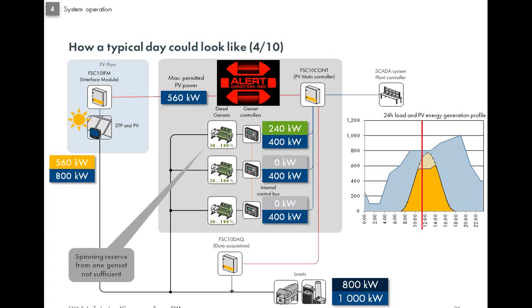Now let's assume that one generator tries to shut down because it thinks that it will take care of the load entirely by itself. If that starts to happen, our system will give an alarm and it will make sure that there is sufficient spinning reserve present in the generators available to take care of the load in any situation. And by any situation I mean that the solar suddenly goes out or clouds come in or so on.